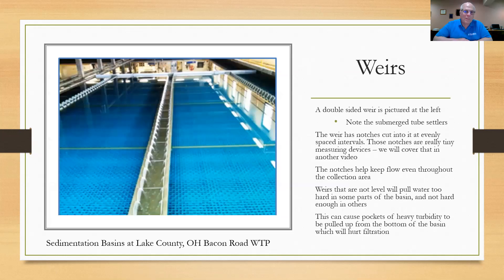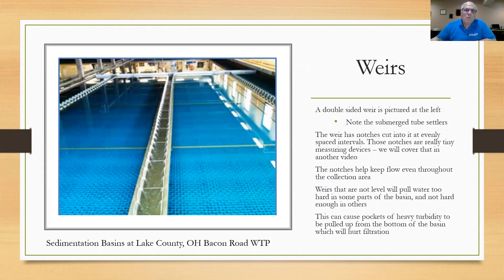Here's a picture of an actual double-sided weir at the Lake County, Ohio Bacon Road Water Treatment Plant — we thank them for letting us use their picture. You can see the weir is going perpendicular to the flow, and the weirs have notches on both sides, pulling water from the top portion. Notice they're sitting on top of a set of tube settlers. When I measure the length of this weir, I get to multiply it times two to get my actual weir length.